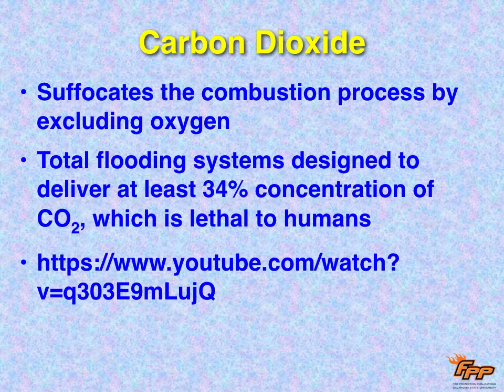CO2 is really good. It puts out the fire by suffocating it. It displaces the oxygen. So you don't want to be in a flooding system of CO2 because it's lethal to humans. It's not the CO2 that's going to kill you. It's the fact that it pushes all the oxygen out. Here's another link for you to check out. It's kind of cool how CO2 flooding systems work, but there's CO2 extinguishers too, and CO2 itself is a propellant. And so when it's going from liquid to gas, it has pressure with it. So sometimes we use CO2 to propel the dry chem product out of an extinguisher.